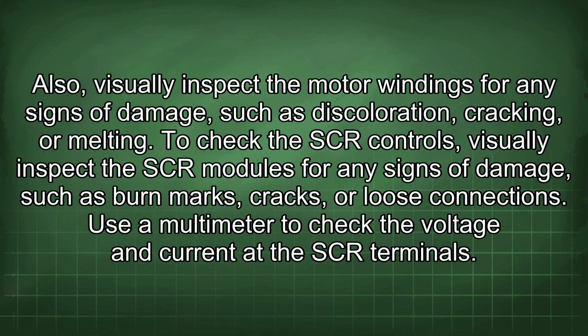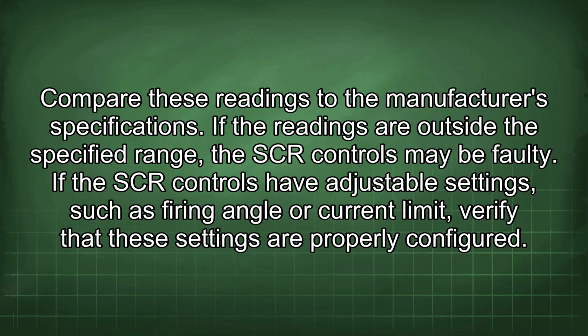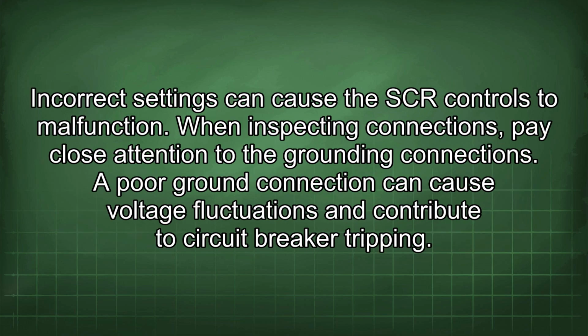To check the SCR controls, visually inspect the SCR modules for any signs of damage, such as burn marks, cracks, or loose connections. Use a multimeter to check the voltage and current at the SCR terminals. Compare these readings to the manufacturer's specifications. If the readings are outside the specified range, the SCR controls may be faulty. If the SCR controls have adjustable settings such as firing angle or current limit, verify that these settings are properly configured. Incorrect settings can cause the SCR controls to malfunction.